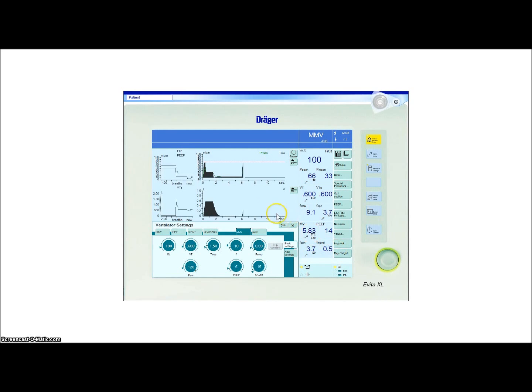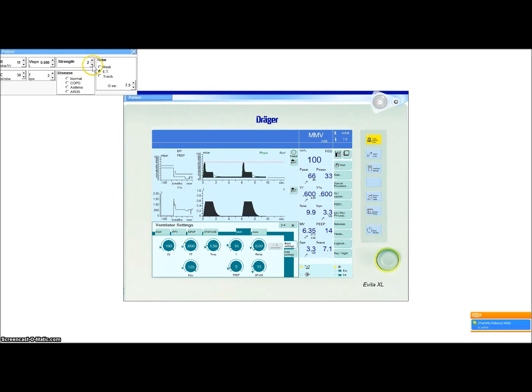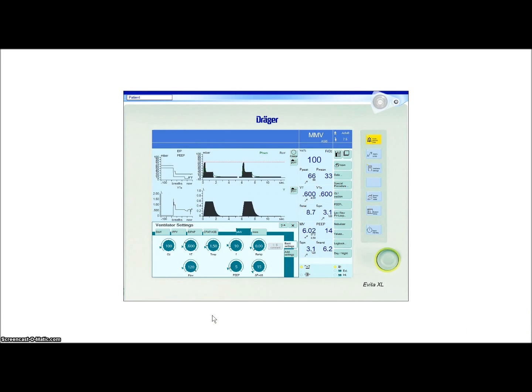So, if he wakes up and starts breathing on his own, he'll get breaths. He can breathe on his own with pressure support, if desired, hence the ASB symbol. But if he's not able to breathe, and he starts drifting in and out of consciousness or drifting into sedation, he'll start getting the mandatory rate, or enough to keep this minute volume above 10, which is not doing a very good job because of this compliance. But it's going to get there. And this will be good if he stops breathing altogether. Notice the minute volume is going up.